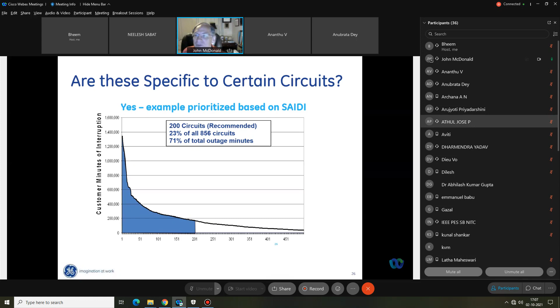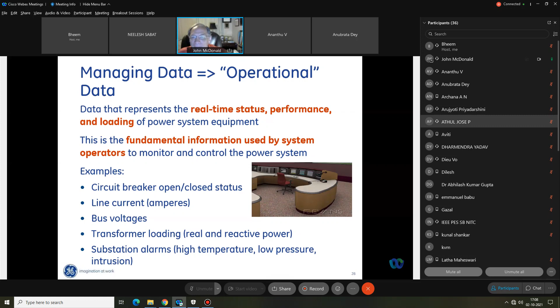To get full value from our investment in protective relays and microprocessor-based devices, there are two types of data in such a device. What we typically focus on is only the operational data—the real-time data operators in the control center use to monitor and control the grid, things like real-time status, performance, and loading. These are points of information and time series of points: circuit breaker open/close, current, voltage, real and reactive power, alarm information. This is what we've used for many years, collecting it in the field and sending it up to the control center.